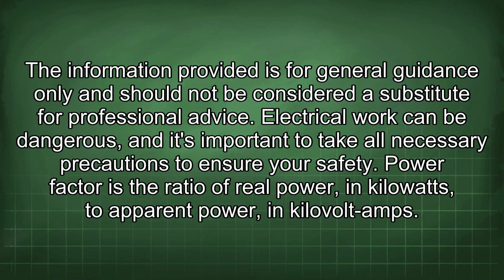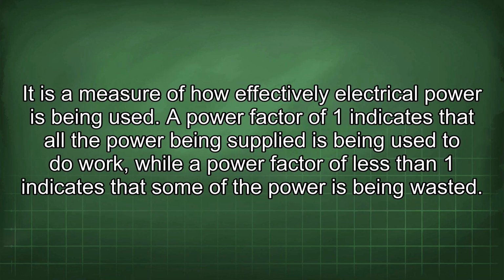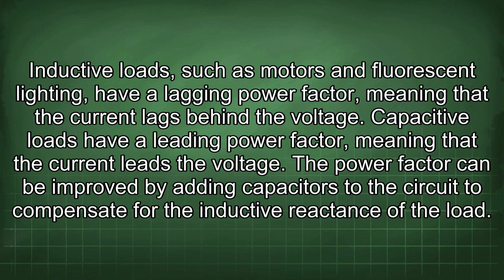Power factor is the ratio of real power in kilowatts to apparent power in kilovolt amps. It is a measure of how effectively electrical power is being used. A power factor of 1 indicates that all the power being supplied is being used to do work, while a power factor of less than 1 indicates that some of the power is being wasted. Inductive loads, such as motors and fluorescent lighting, have a lagging power factor, meaning that the current lags behind the voltage. Capacitive loads have a leading power factor, meaning that the current leads the voltage.